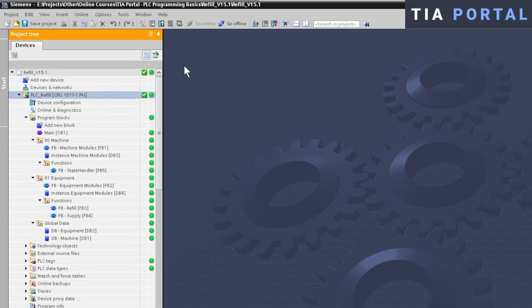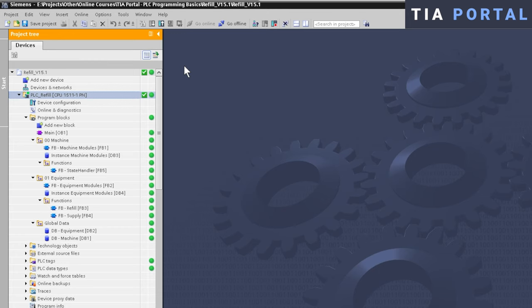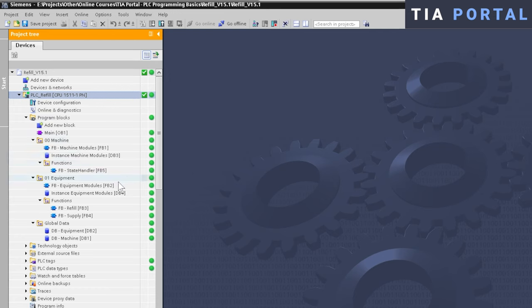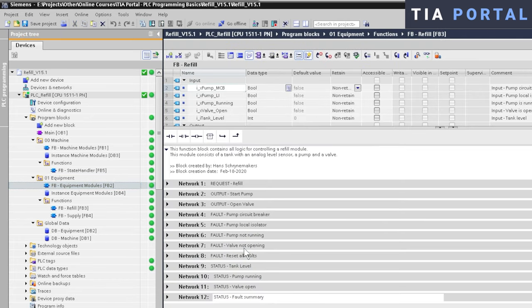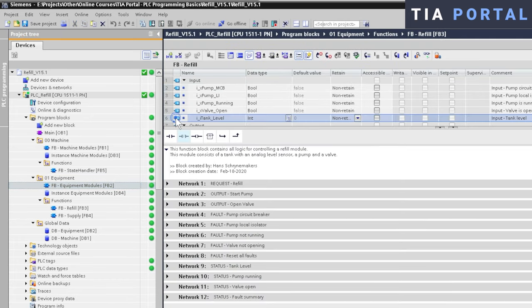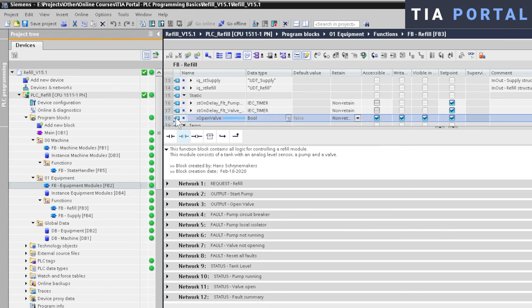Here I am inside the TIA Portal project view. I downloaded my application and I went online. Can you see those green indicators behind every block? At the moment all of them are green and that tells us that all blocks are consistent. There are no differences between the online project and the offline project. Now we are going to make a small change in a function block. Let's go for example to FB equipment modules and make a change inside the FB refill. We can delete this open valve variable in the static area.